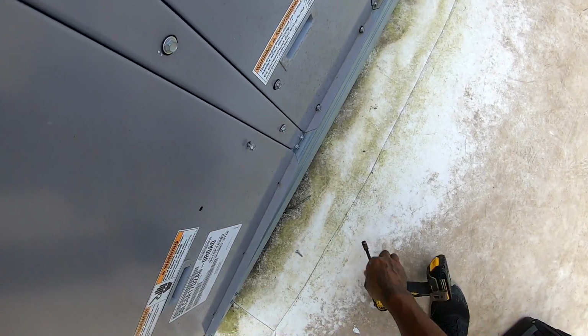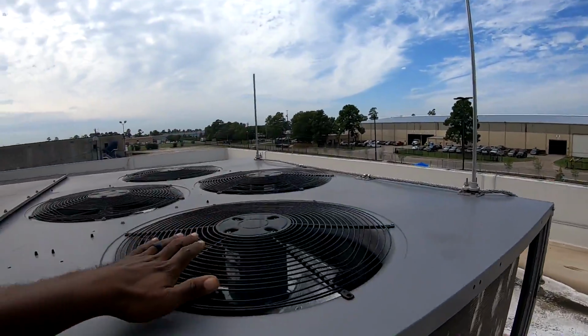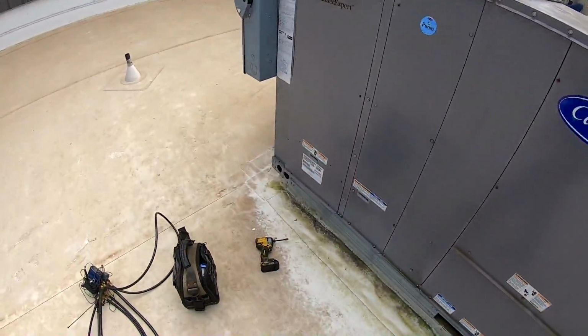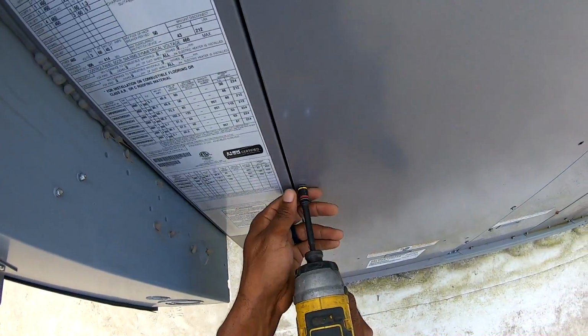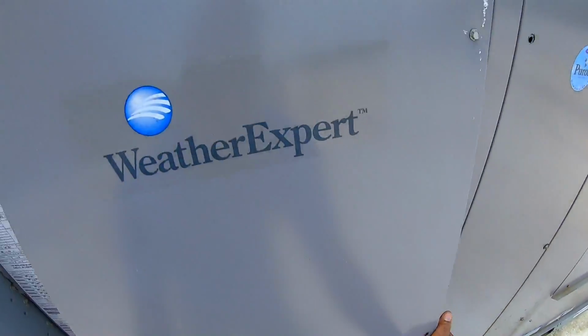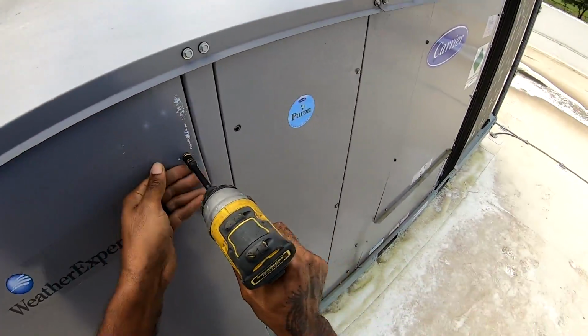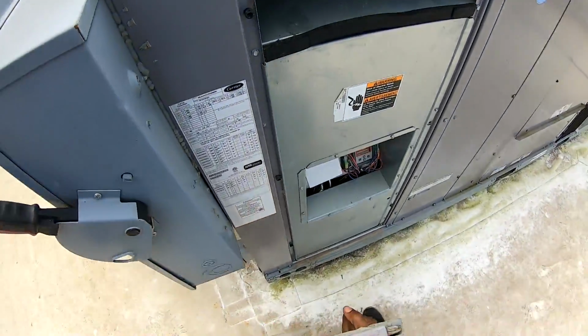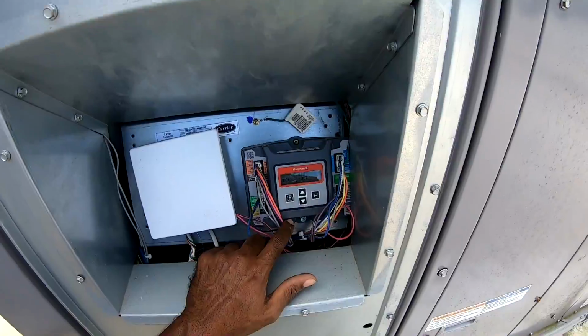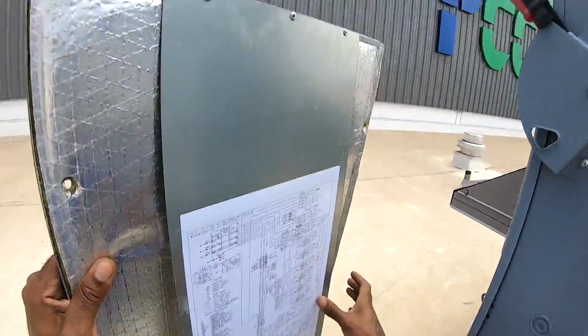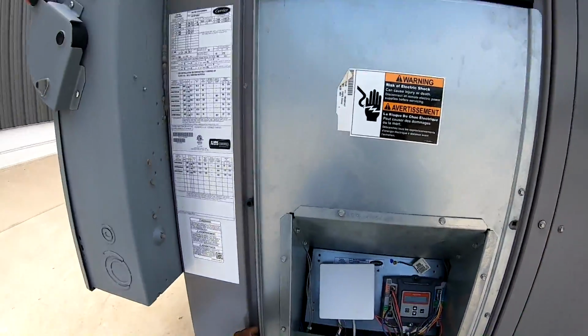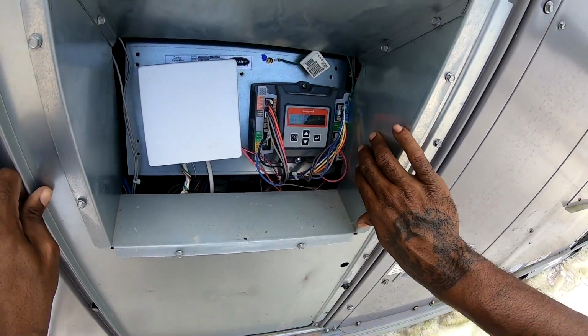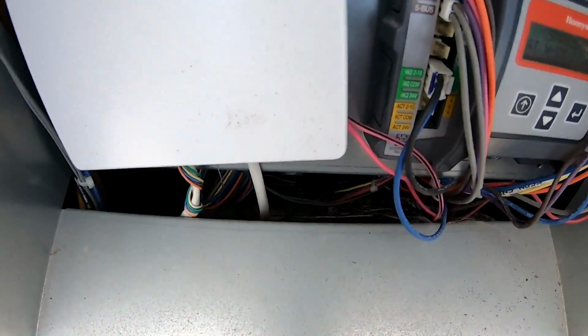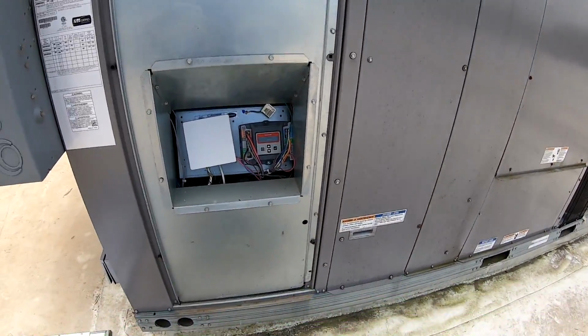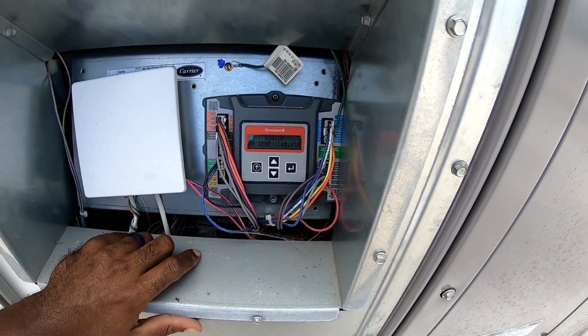It just kicked on. I see that fan not speeding up at all, so I don't know if it's bad caps or what. The wind is kind of blowing, so I don't know if that's helping it or what. Let's see what we got in there. Alarms. Got status on. Something's in the way there. Outside air temperature 85.